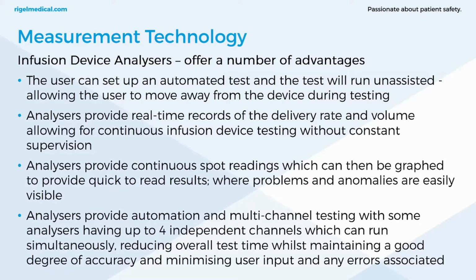So what's commonly carried out during a test: if you were to push start, you would get your instantaneous values, your mean values, but then you could switch to the graph to see if you're getting any anomalies throughout the time of the test. So it's worth having that screen up to see if anything's gone wrong. Analyzers also provide automation and multi-channel testing, with analyzers having up to 4 independent channels, and they can run simultaneously, and this reduces overall test time whilst maintaining a good degree of accuracy and also minimizing user input and any errors that could occur.